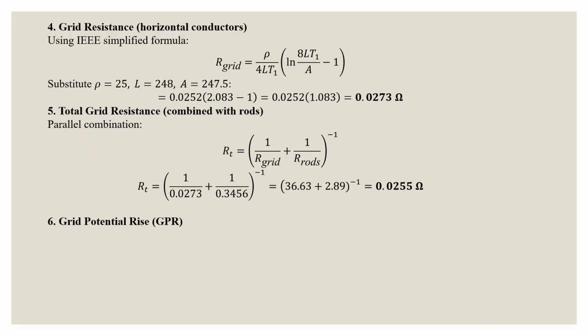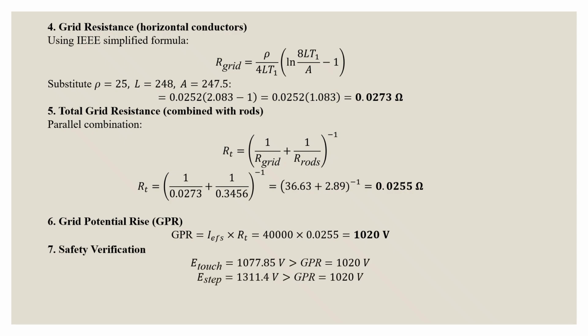Then we have to calculate grid potential rise, GPR. So as shown earlier, the formula for GPR is current into resistance, which is 1020 volts. Now we have to do safety verifications. As we have calculated the touch and step potentials, which is this, and as we can see, they are well within the limit of GPR. So it's better to say the system is safe.